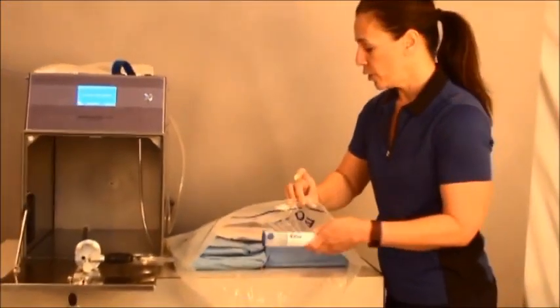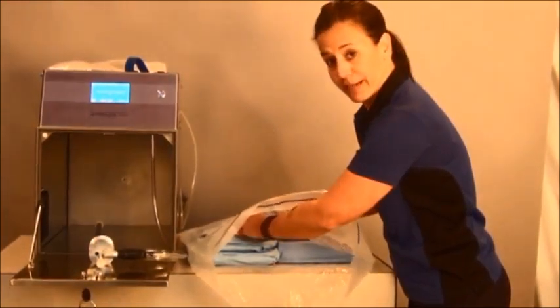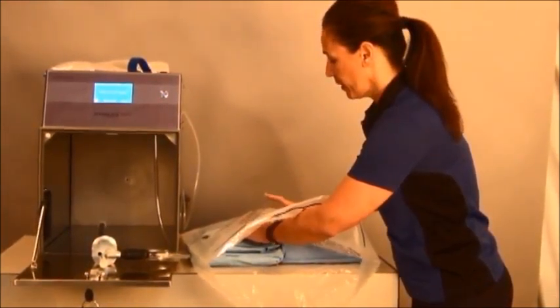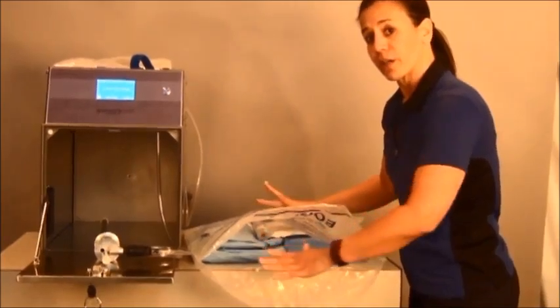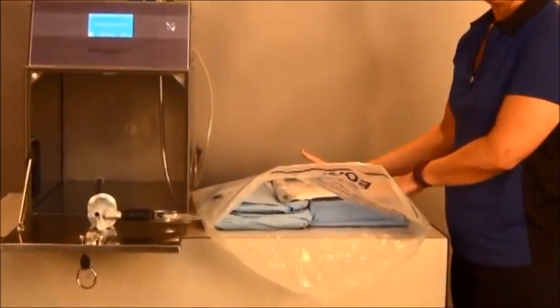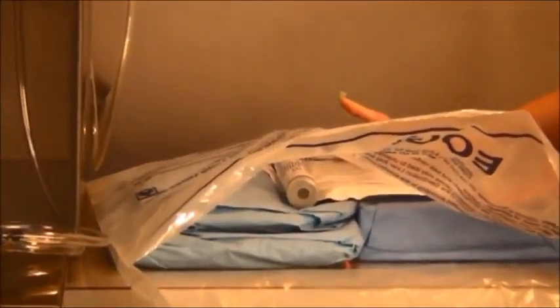Again, you want to put your gas cartridge in the same place every time you run a cycle, and you want to make sure it's somewhere towards the top so it can be easily accessed during the sterilization cycle.